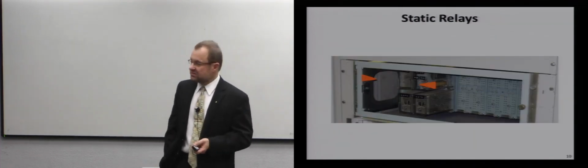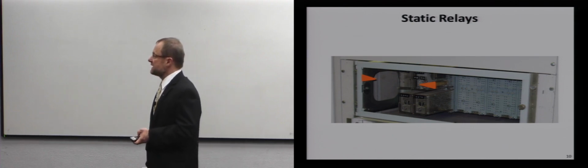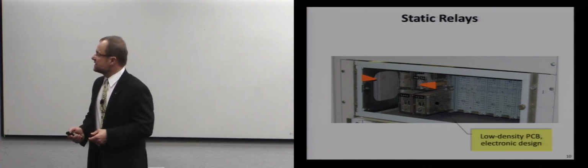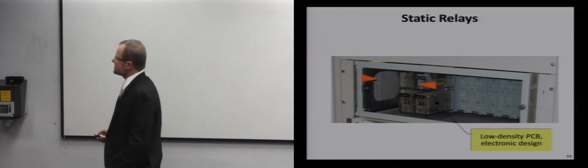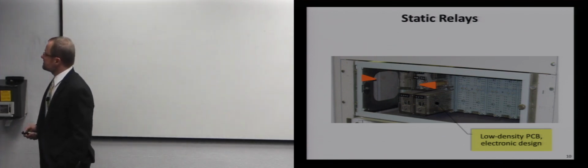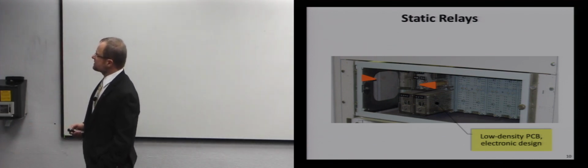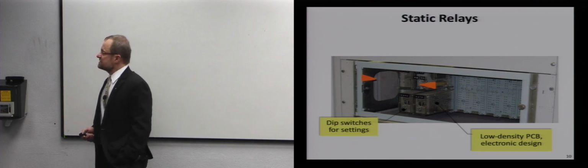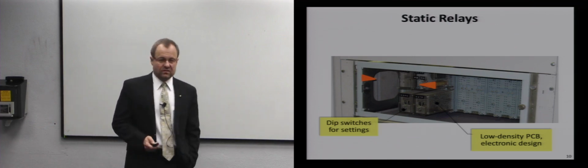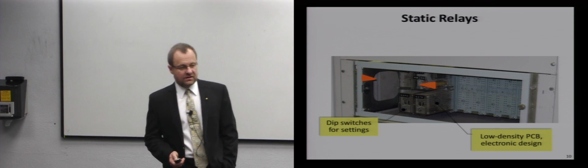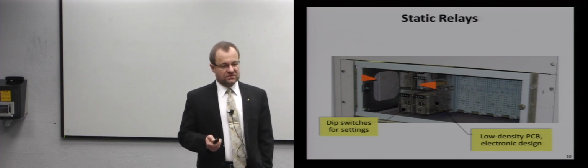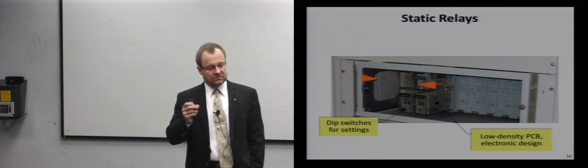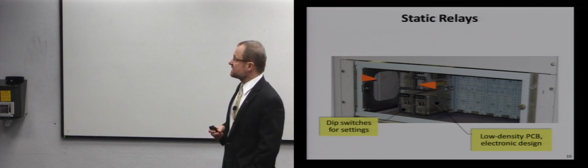This is an example of a static relay, and you could see through that transparent cage that there is a low-density printed circuit board. There are dip switches for settings. If you wanted to move that overcurrent relay to respond from, say, 2 amps to 3 amps, you would move the dip switches. Those are the settings.